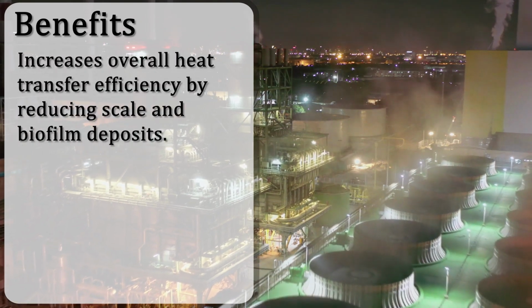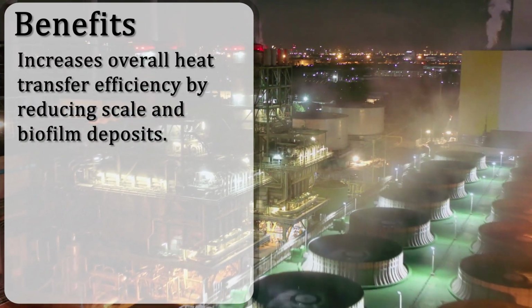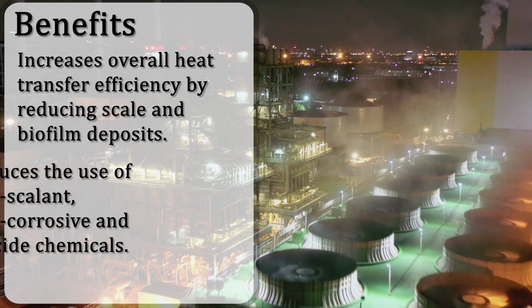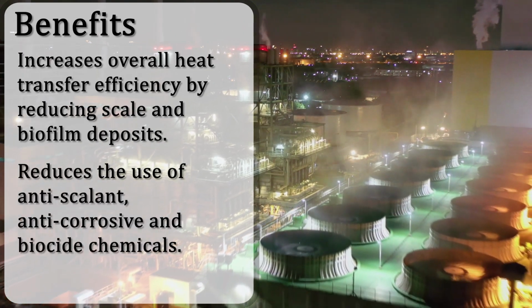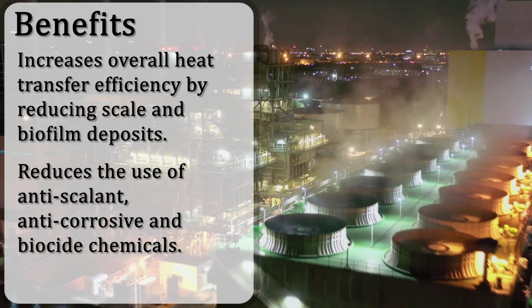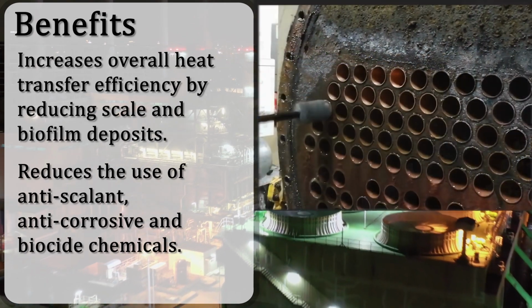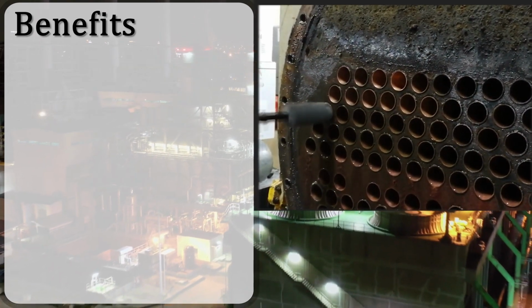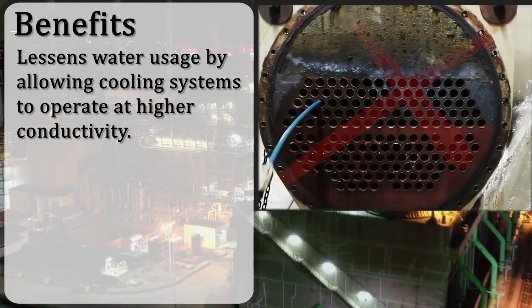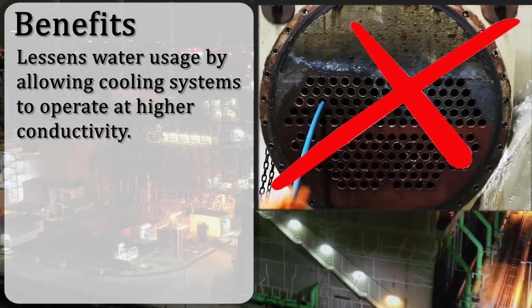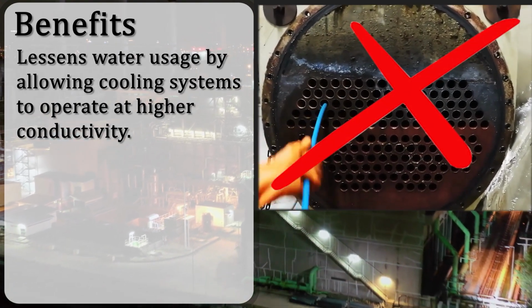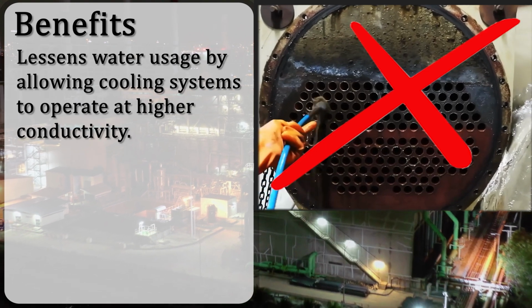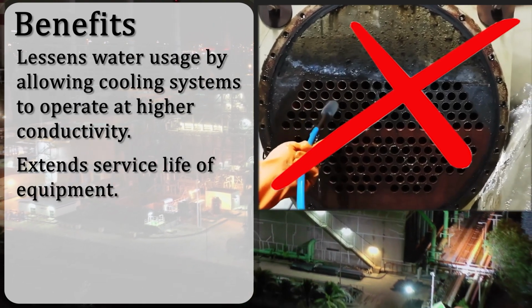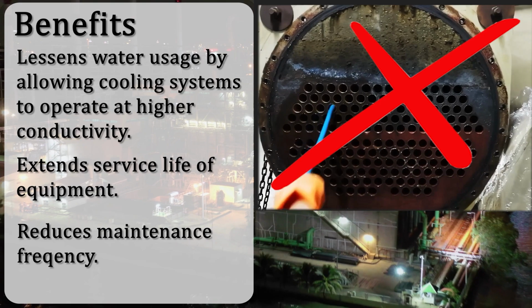Benefits: increases overall heat transfer efficiency by reducing scale and biofilm deposits, reduces the use of anti-scalant, anti-corrosive, and biocide chemicals, lessens water usage by allowing cooling systems to operate at higher conductivity, extends service life of equipment, and reduces maintenance frequency.